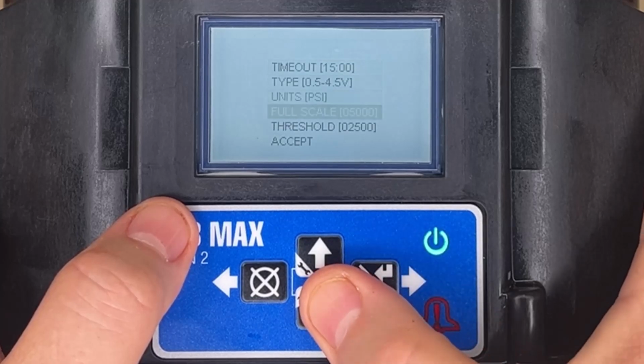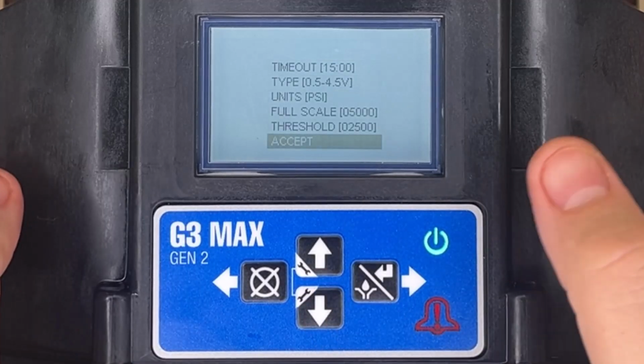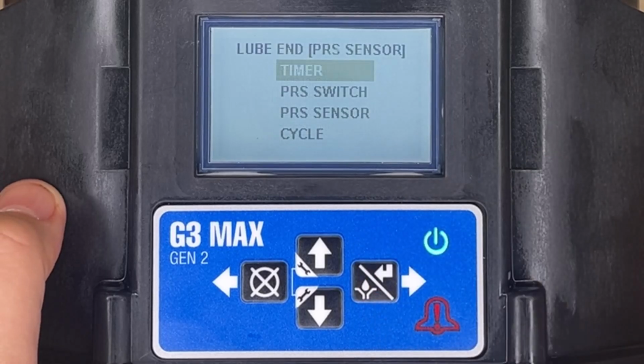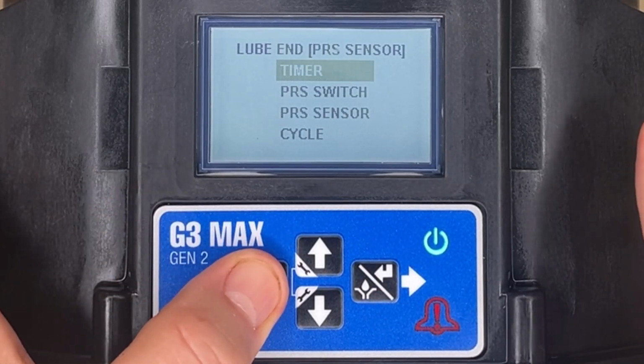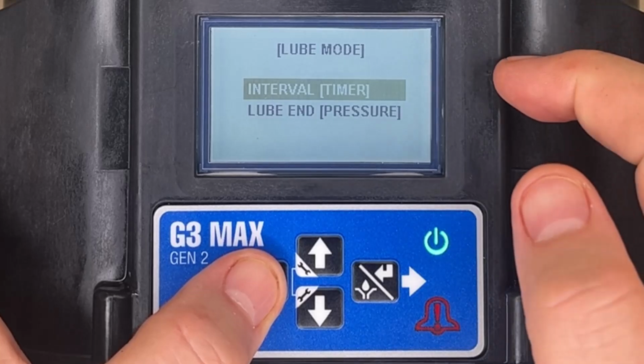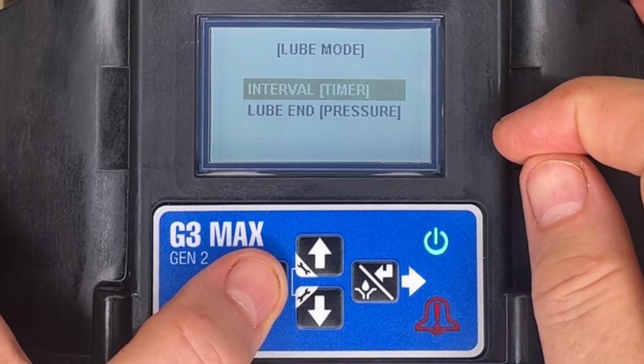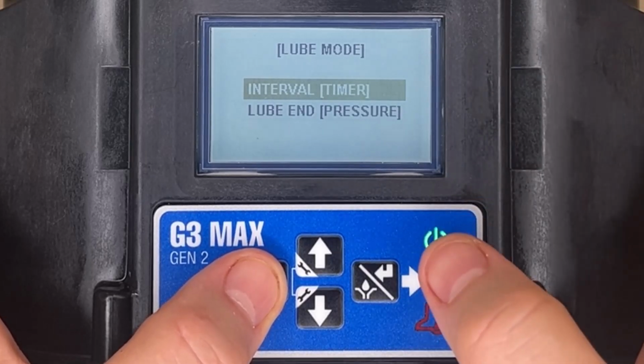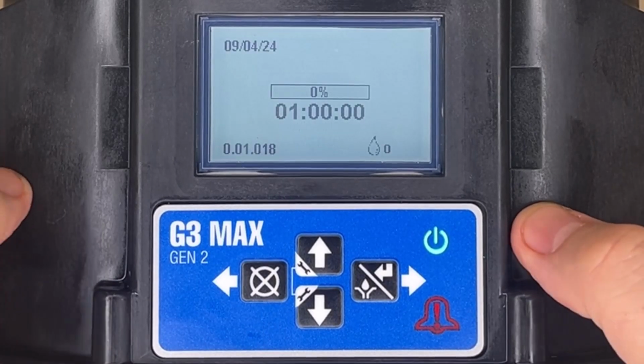And then we're going to go down to accept. Once the cursor's on accept, press the right arrow to save all those settings. And now we can back out, and it shows that our interval is a timer and our lube end is pressure. And that is how you set up a pressure-based system.